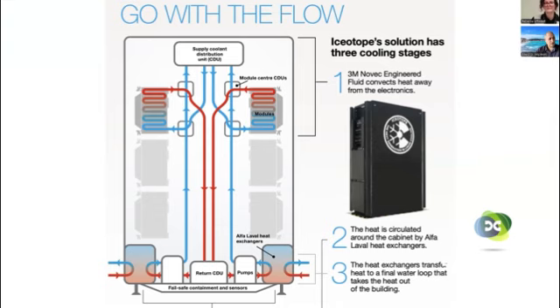And particularly, what is important is that they have immersion at each server level. So there were modules, and the water inside was connected with heat exchangers, which were connected with the facility. The most important thing I want to mention is that the technology in 2015 allowed a reduction in the energy consumption of the servers, which was something special, because with air you use it as it is, but with that approach you can reduce server energy consumption by 10-15%, which is not achievable with air cooling.